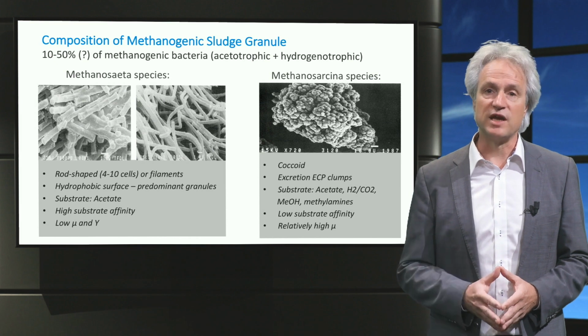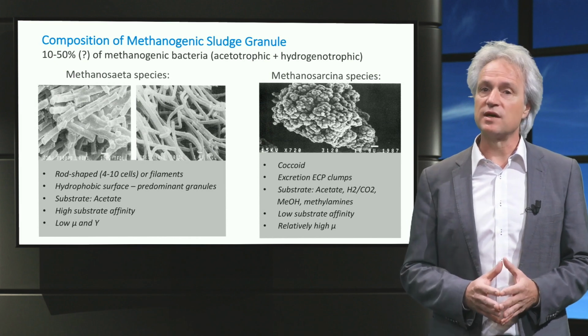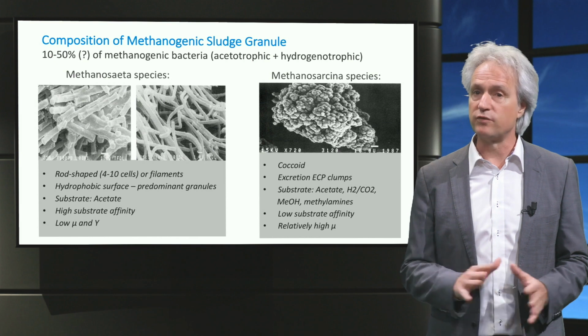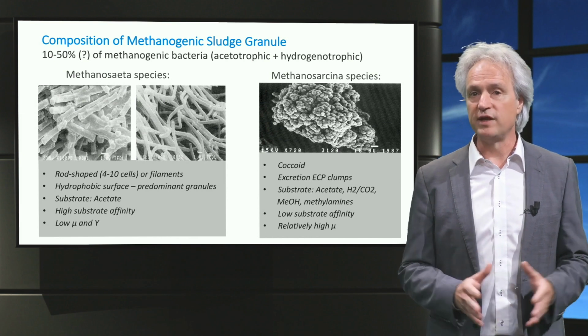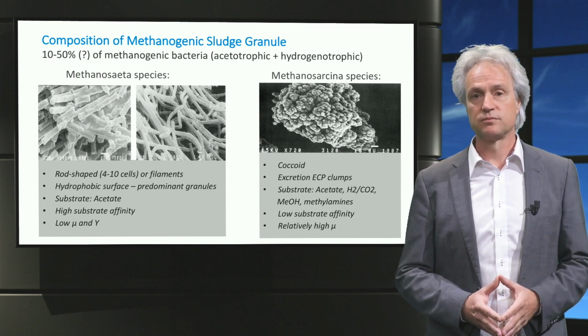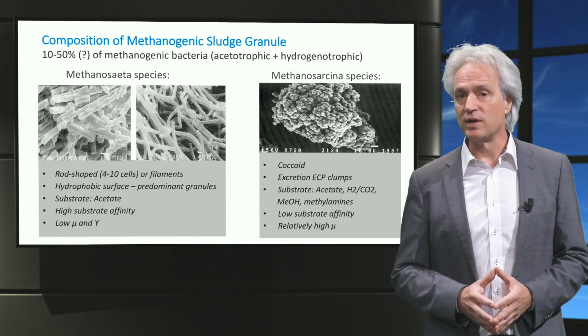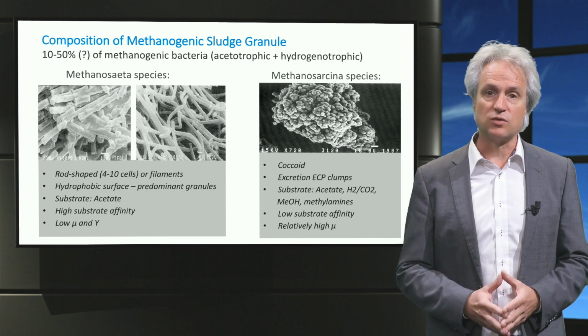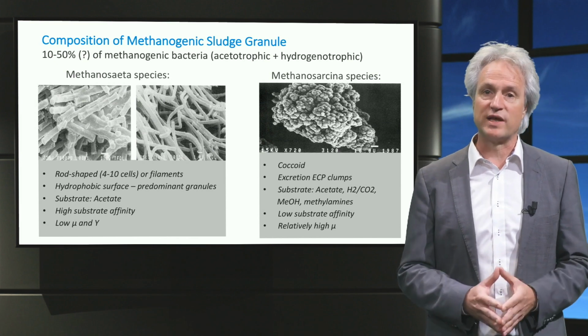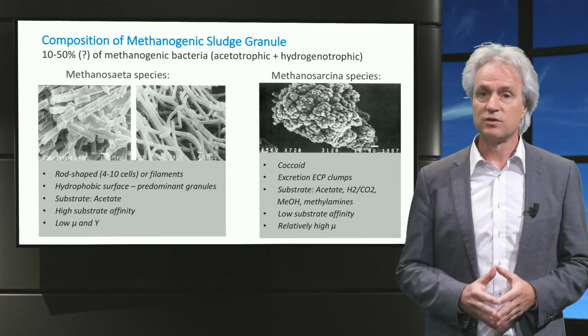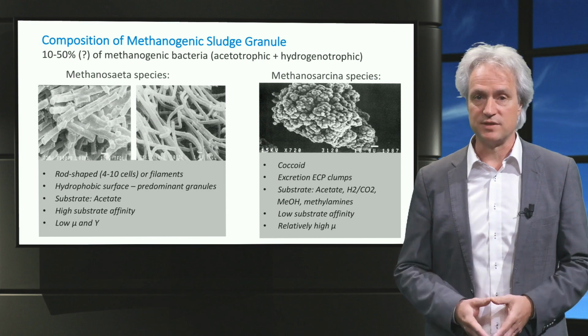As shown in the previous table, Methanosaeta species are characterized by the lowest growth rate of all the trophic groups involved in the anaerobic conversion process. Hence, particularly during the startup, reactor operation and increments in loading rates are governed by the growth and development of a stable acetoclastic methanogenic sludge bed, consisting of Methanosaeta species.